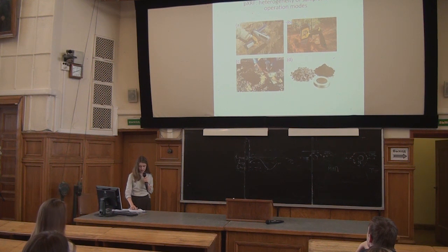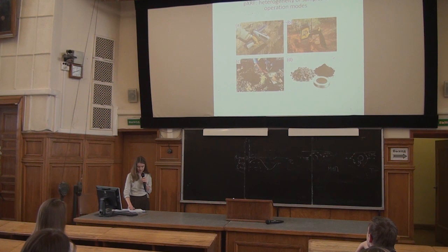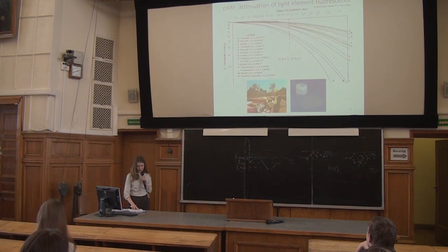If hard media is fragmented and milled, like in picture C, analysis quality improves. And only with lab-type preparation, when material is dried, sieved, and homogenized, can we expect quantitative analysis within the instrument's performance limits. In some advertising booklets, we can find a picture of an operator running the analysis through a plastic bag.